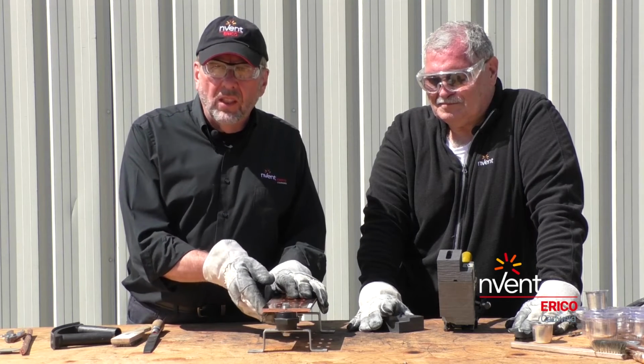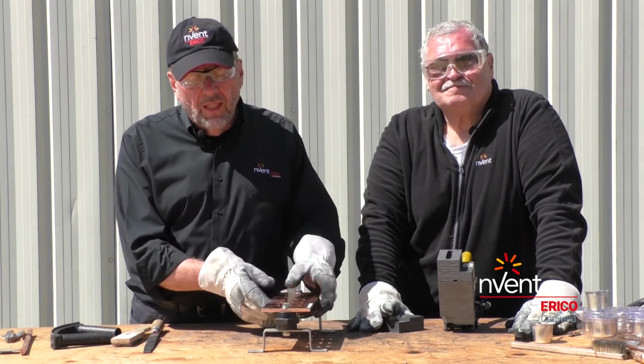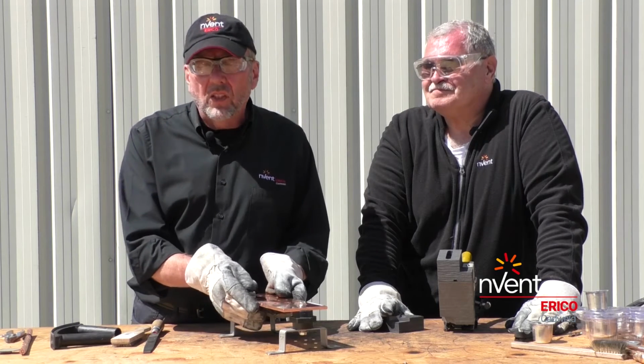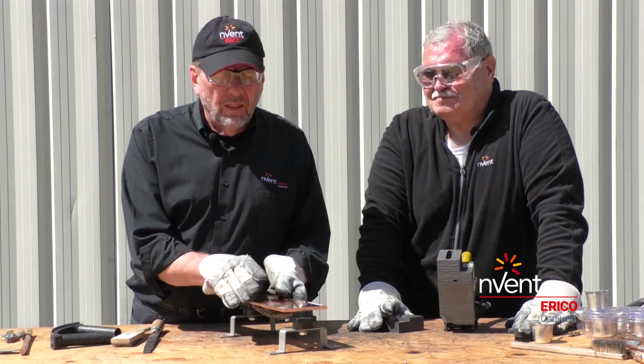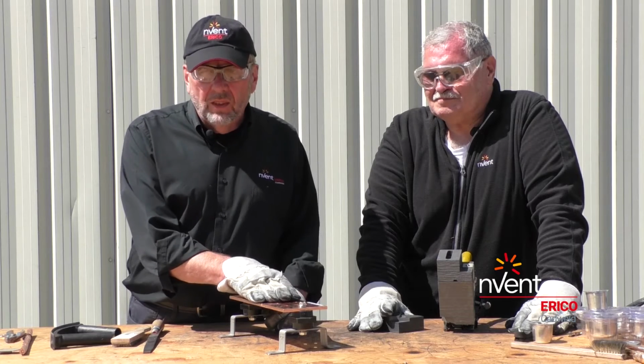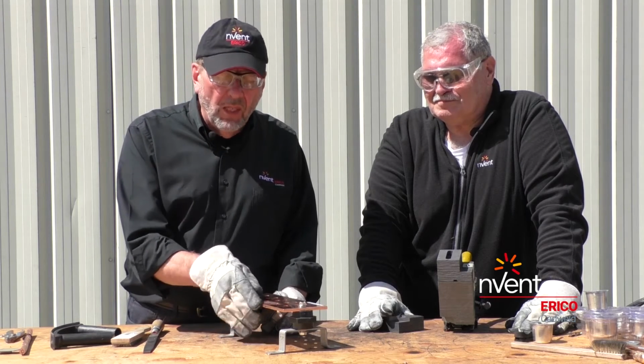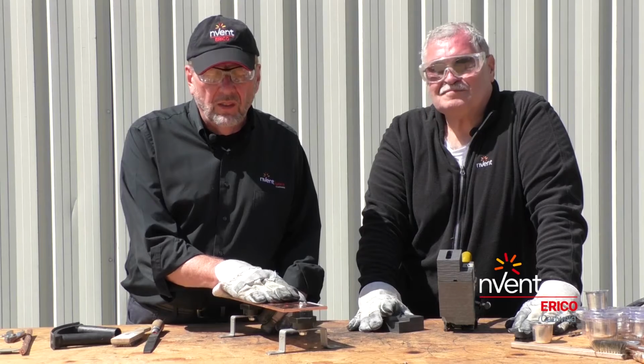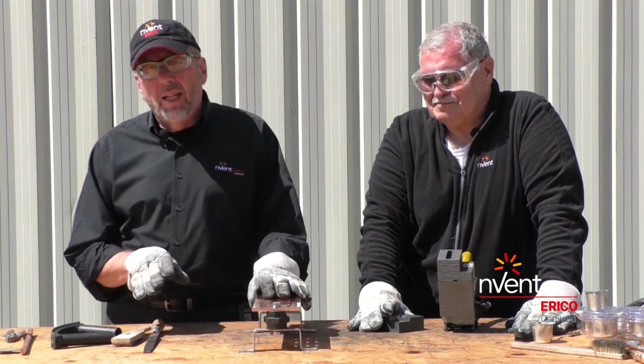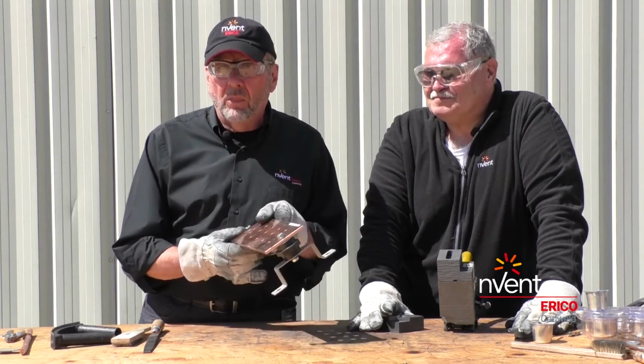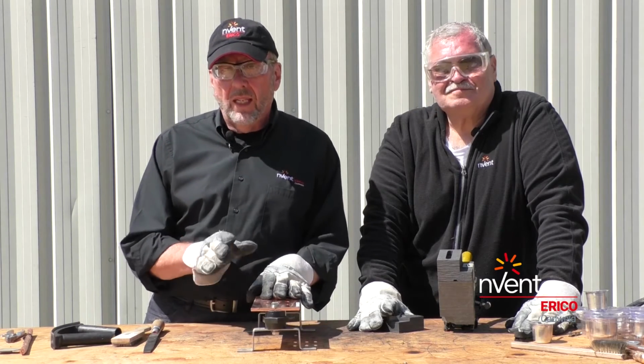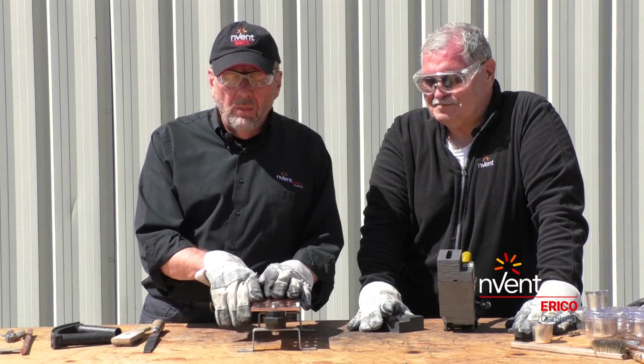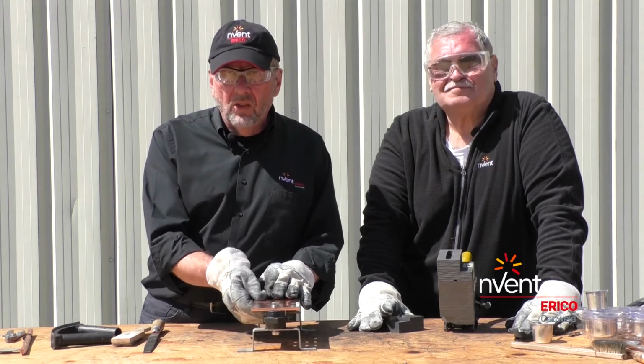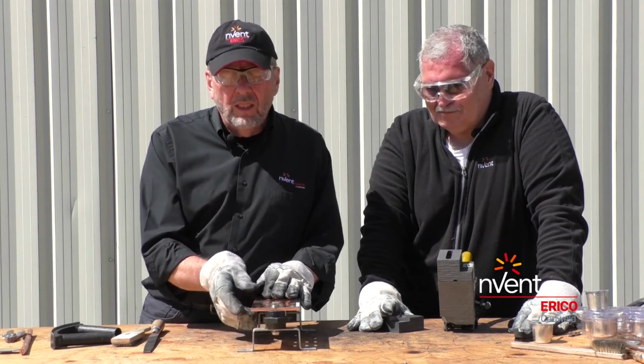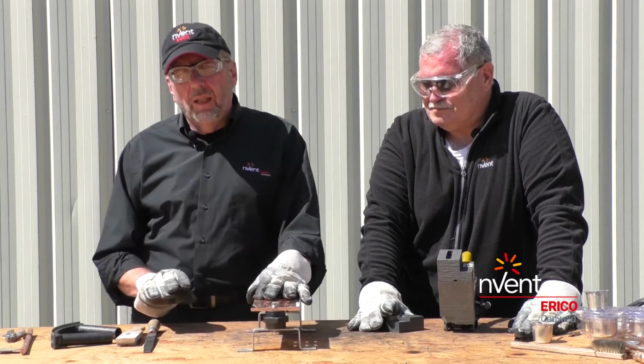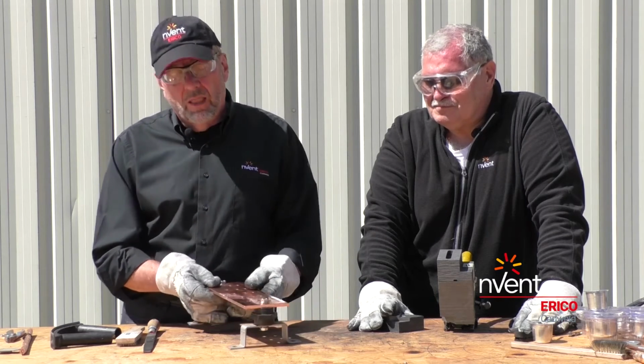We try to weld to the edge of it instead. In doing that, we're attacking a much smaller cross-sectional area of this copper object, so we're certainly much more likely to get some melt here at the edge than we would on the flat face. This would apply to an equipment ground bar like this, an earth bar, or a copper strip. Very often we make these connections on the edge of the copper object so we can get good melt. Our example here today is an equipment ground bar.